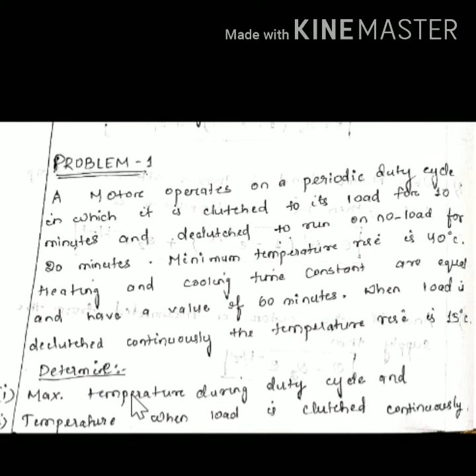So here the problem is: a motor operates on a periodic duty cycle in which it is clutched to its load for 10 minutes and declutched to run on no load for 20 minutes. The minimum temperature rise is 40 degrees Celsius. Heating and cooling time constants are equal and have a value of 60 minutes. When the load is declutched continuously, the temperature rise is 15 degrees Celsius. So we have to determine the maximum temperature during the duty cycle and the temperature when the load is clutched continuously.